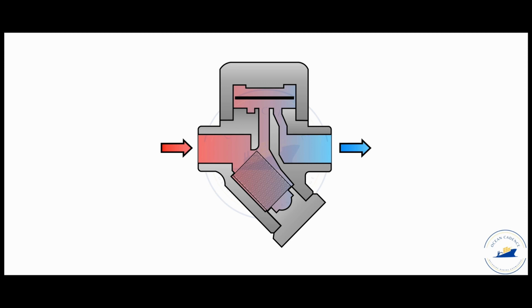So what it will do is when the hot condensate faces a change of curvature and then moves upwards, over here it creates a significant drop in pressure, that is a low pressure region. By doing so, this low pressure region actually creates a suction or pulling force on the disc, thereby disturbing the equilibrium which was created due to the mutual existence of water on the top and the bottom.